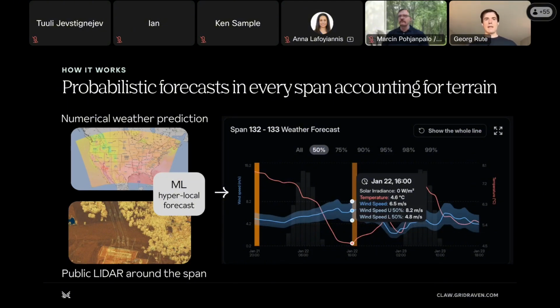So you have full transparency of how the rating is calculated and what the weather conditions were in that rating. This is for one span, and for an entire line you'll have a rating for the line. I should also say the weather prediction works inherently with U and V vectors, so it does both wind speed and direction, not just wind speed.